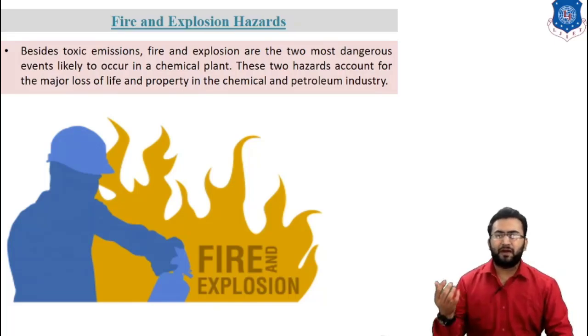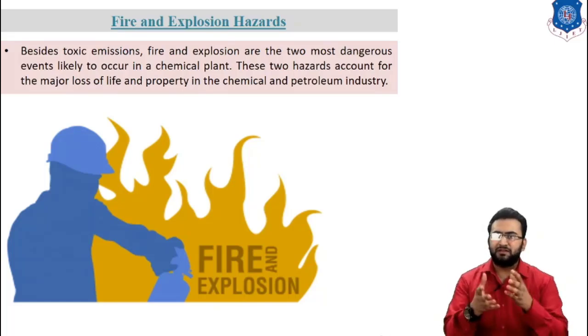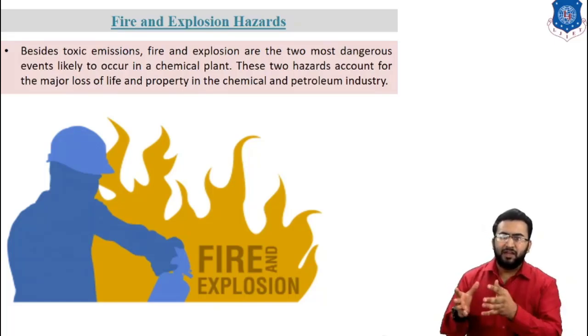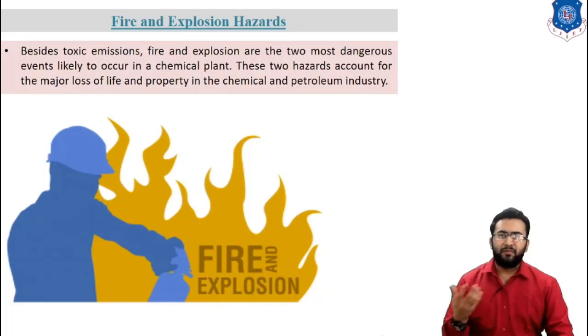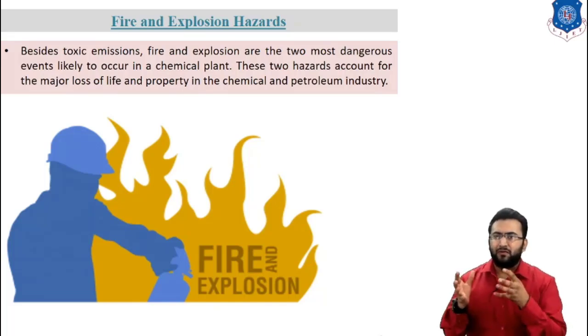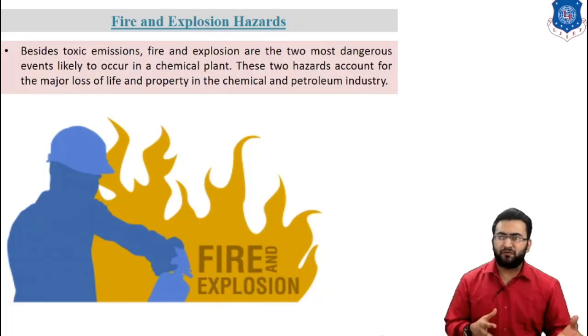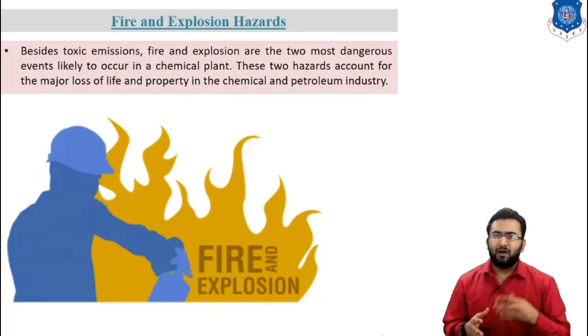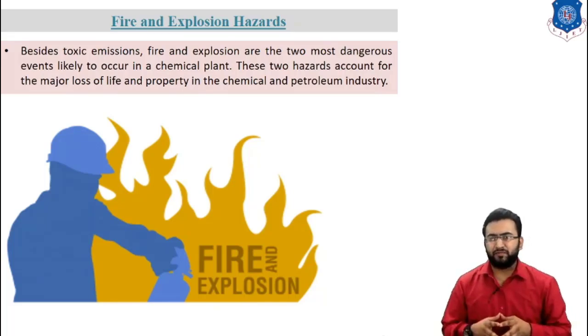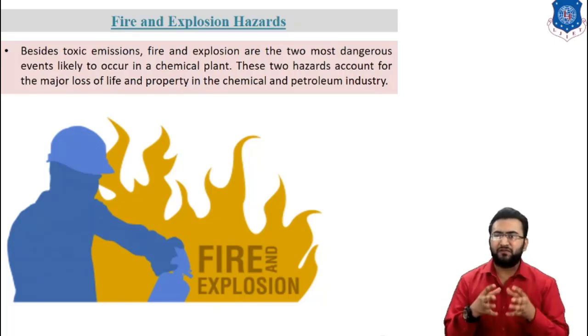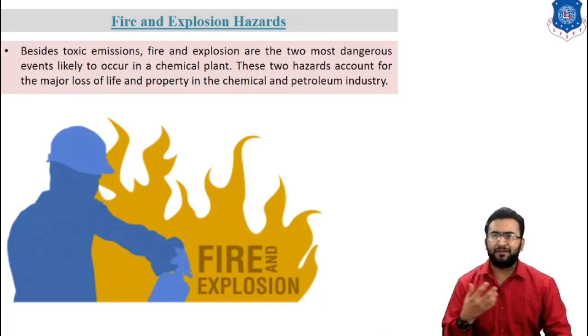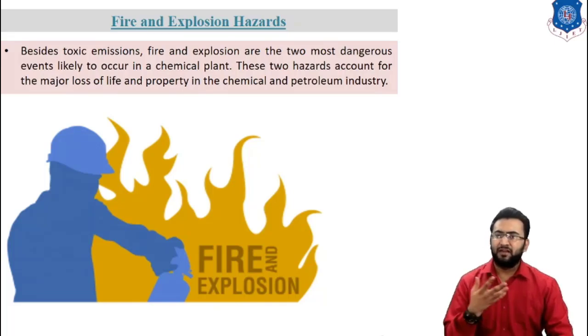Possible sources of fire are reduced by eliminating all unnecessary ignition sources such as flames, sparks, heated material and matchboxes. Smoking, welding, cutting, static electricity, spontaneous combustion, and non-explosion-proof electric equipment are all potential ignition sources. The installation of sufficient fire alarms, temperature alarms, firefighting equipment and sprinkler systems must be specified in design.